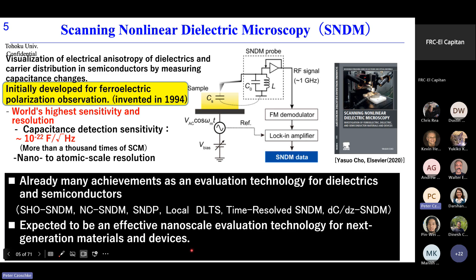Anyway, at first I'd like to introduce the operating principle of this SNDM. This is the original conventional analog type SNDM. Here is the SNDM probe, which consists of a so-called free-running active LC oscillator, whose oscillating frequency is tuned to this LC resonant frequency here. The typical oscillating frequency in this microscope is of gigahertz order. And the metal tip is connected to this tank circuit. And from outside, we apply a usually sinusoidal voltage between tip and sample.